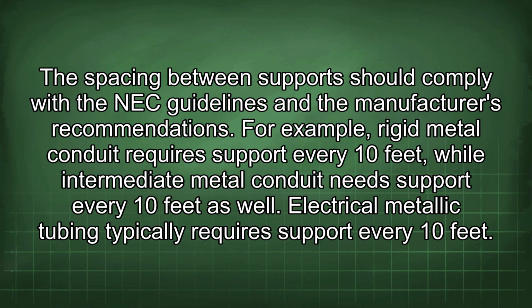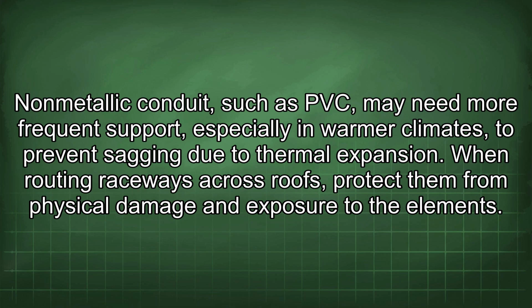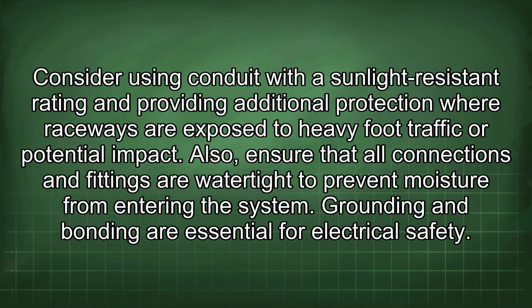For example, rigid metal conduit requires support every 10 feet, while intermediate metal conduit needs support every 10 feet as well. Electrical metallic tubing typically requires support every 10 feet. Non-metallic conduit, such as PVC, may need more frequent support, especially in warmer climates, to prevent sagging due to thermal expansion. When routing raceways across roofs, protect them from physical damage and exposure to the elements. Consider using conduit with a sunlight-resistant rating and providing additional protection where raceways are exposed to heavy foot traffic or potential impact. Also, ensure that all connections and fittings are watertight to prevent moisture from entering the system.